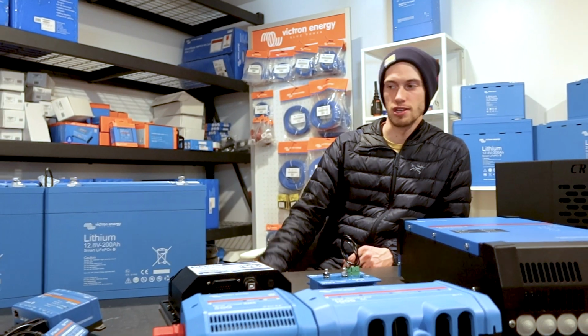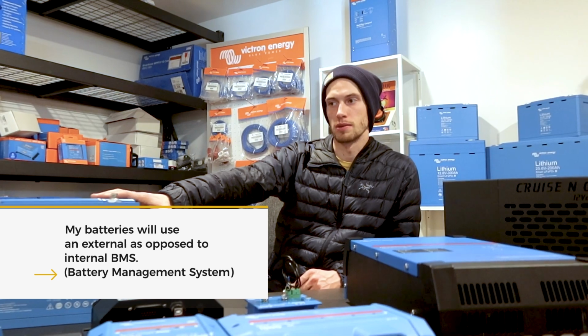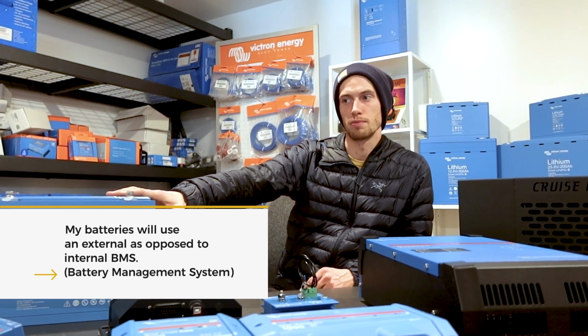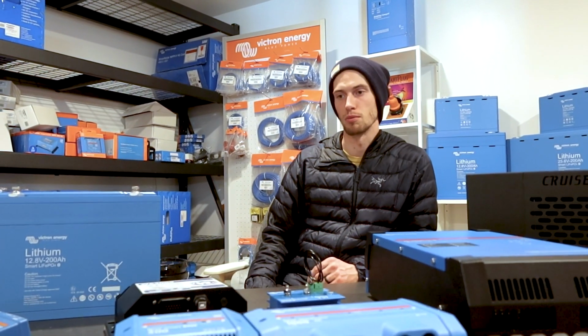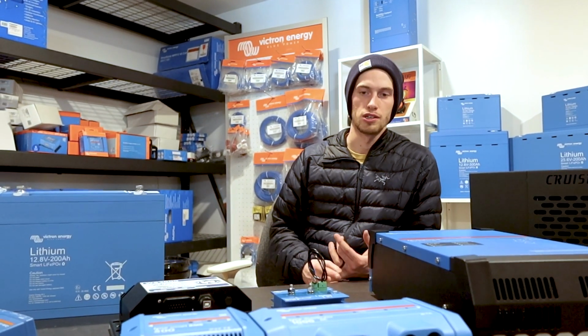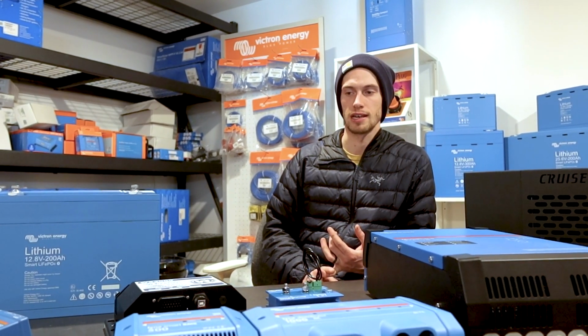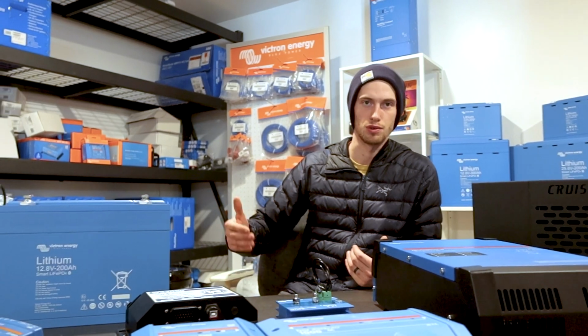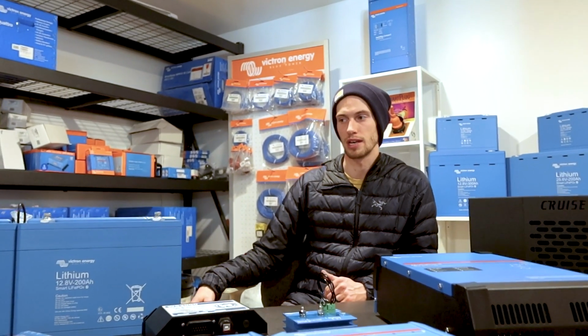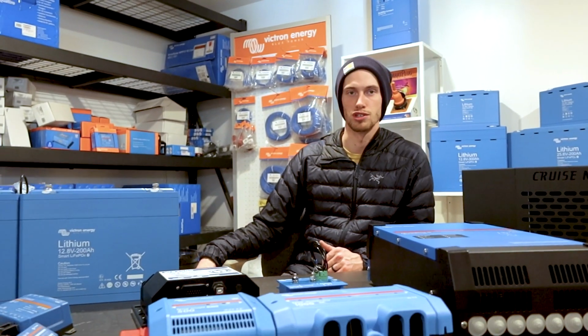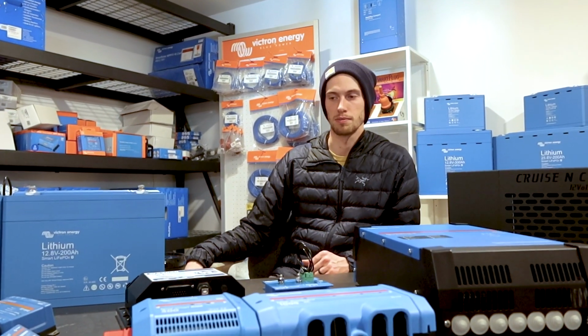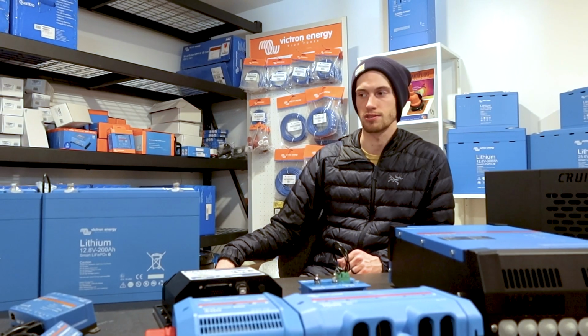The major difference between Victron batteries and other batteries on the market is the external BMS. By removing the BMS from inside the battery, you remove some limitations. First, you get an increase in energy density because you don't need an individual computer in every battery. There's still a balancing board and communication, but it's much more reduced than other batteries on the market that have the contactor inside.